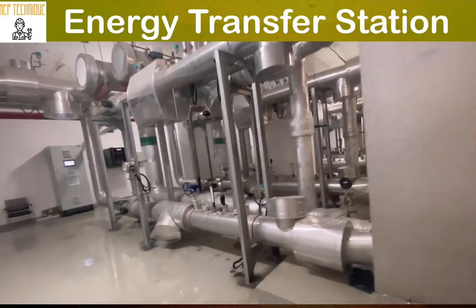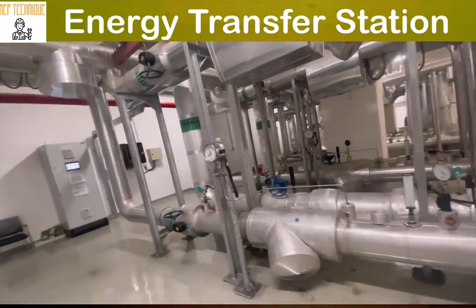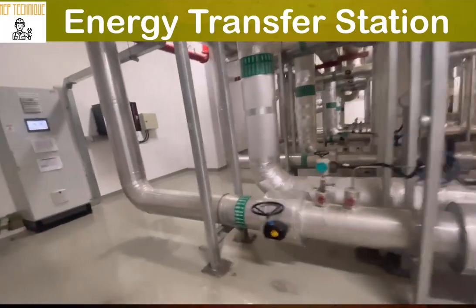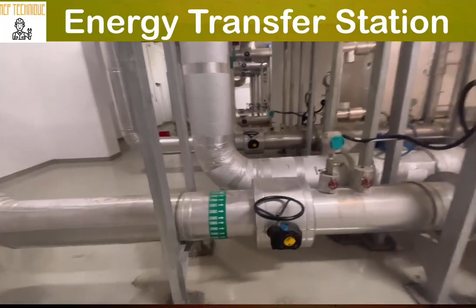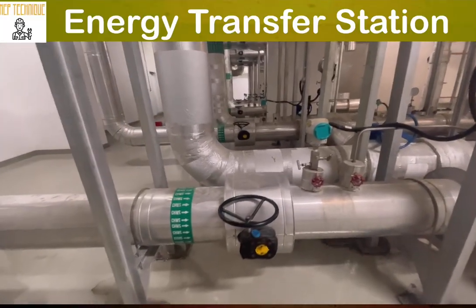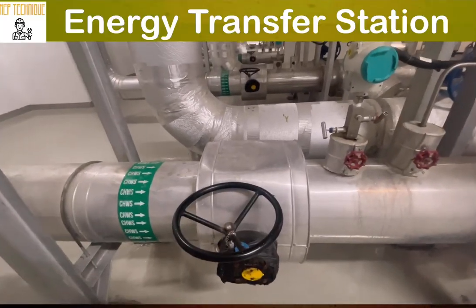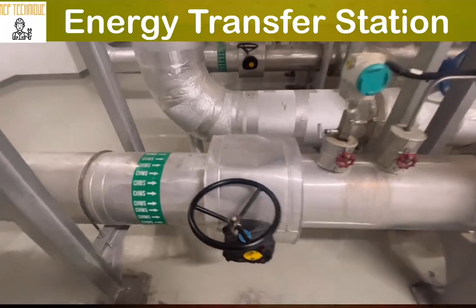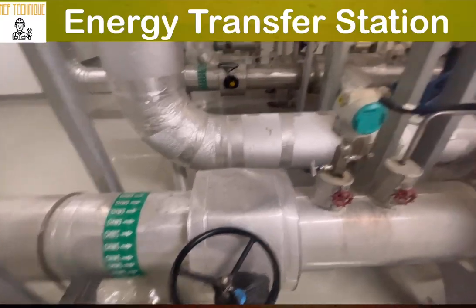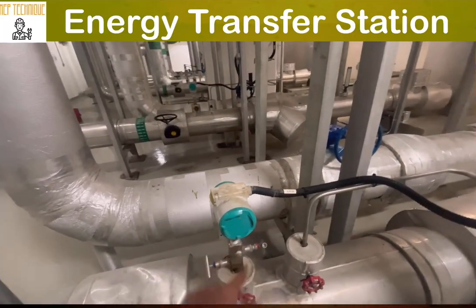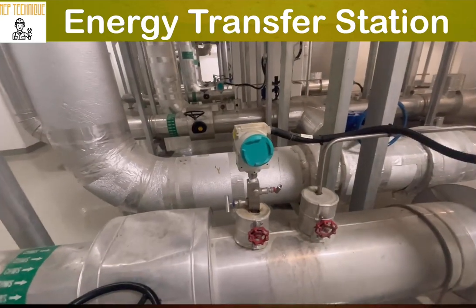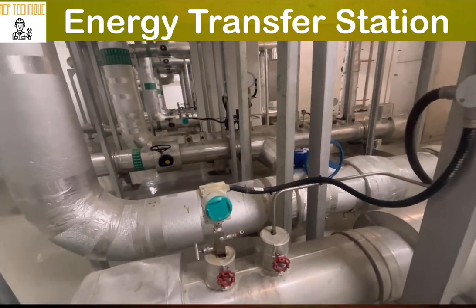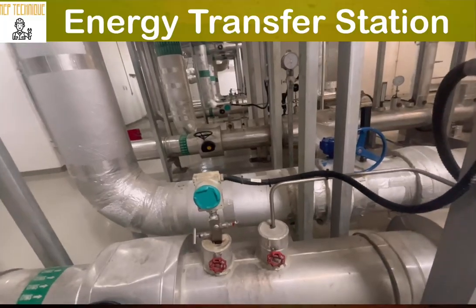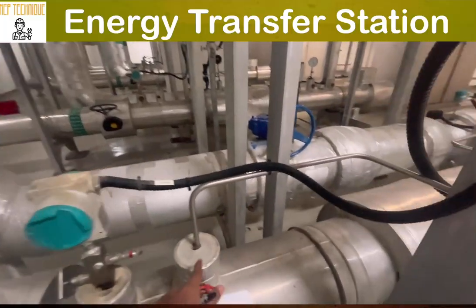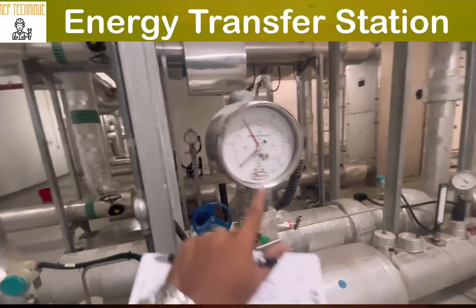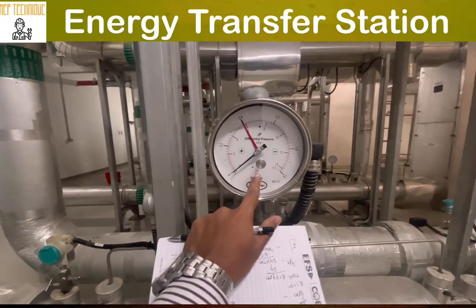So let us discuss what components, isolation valves and regulating valves are installed in the chilled water line. This is the supply connected from the distribution company, and this is the isolation valve, one kind of butterfly valve to isolate the chilled water. Then this is the pressure transmitter you can see here, which is integrated with our DDC panel. DDC means direct digital control. Then this is connected with our DPG, which is also a differential pressure gauge.